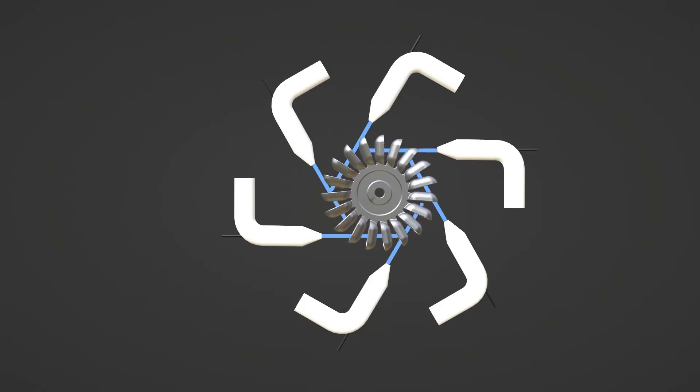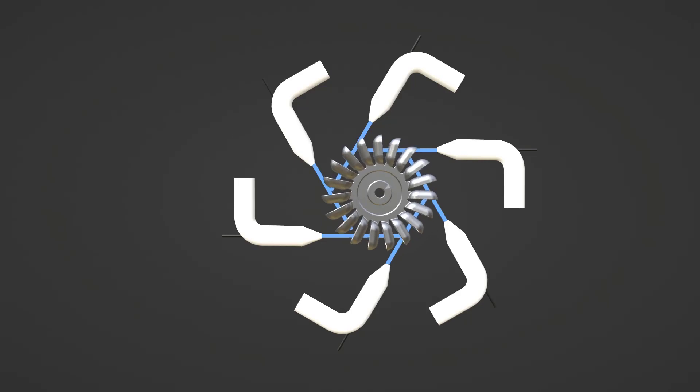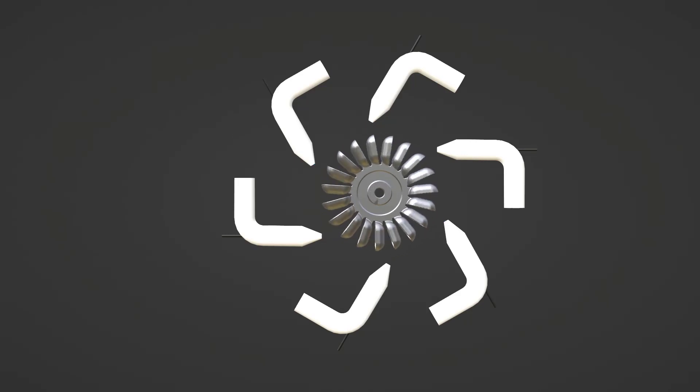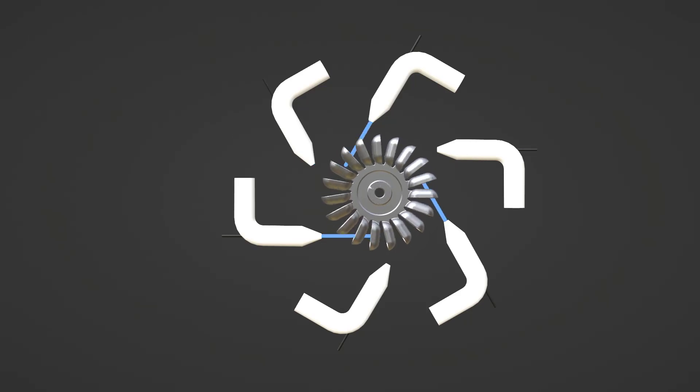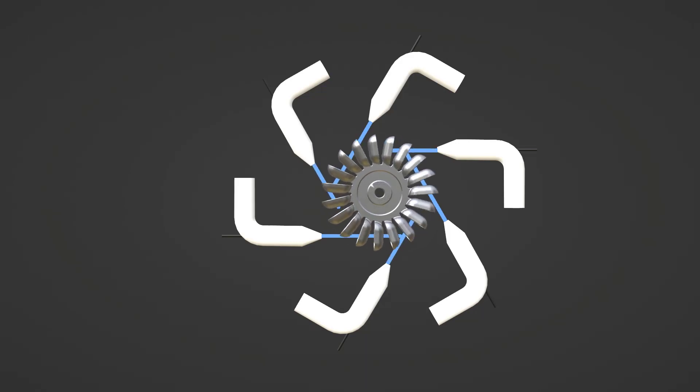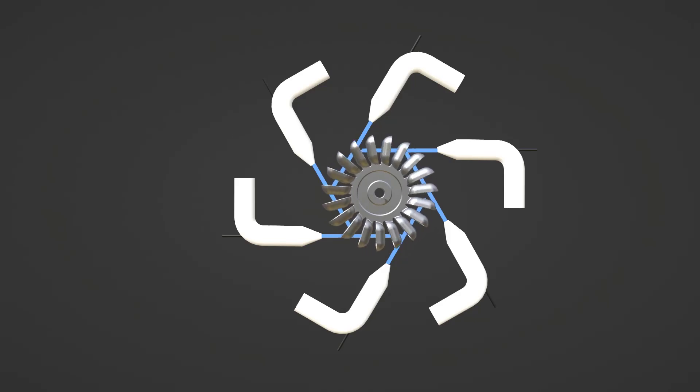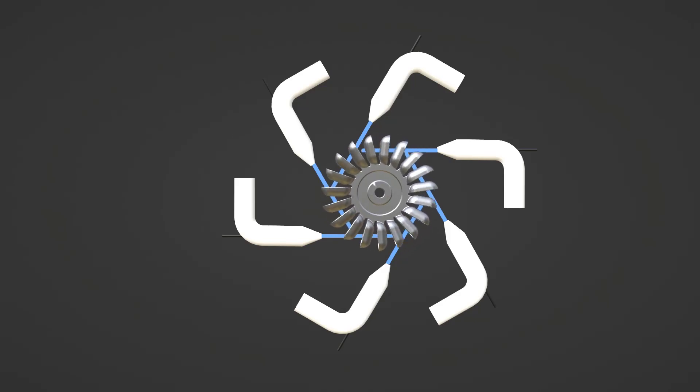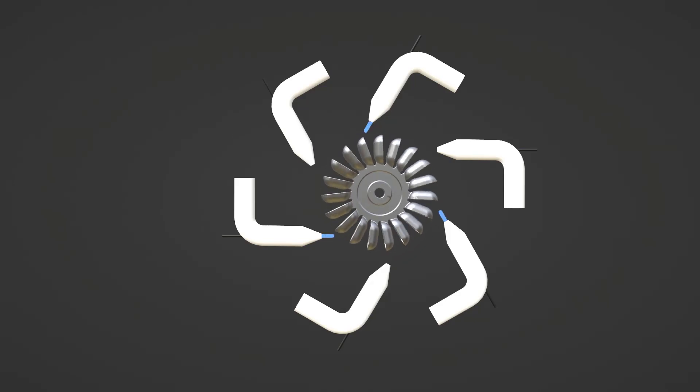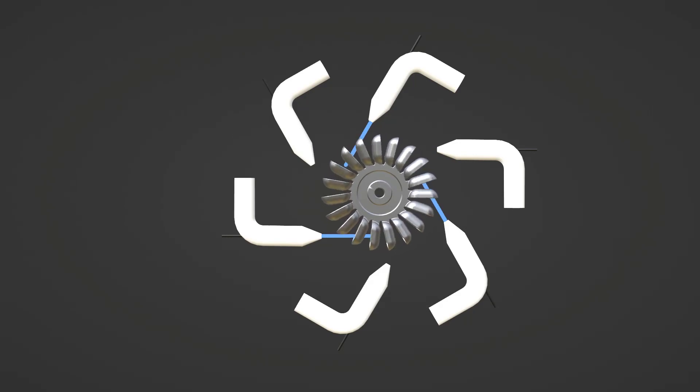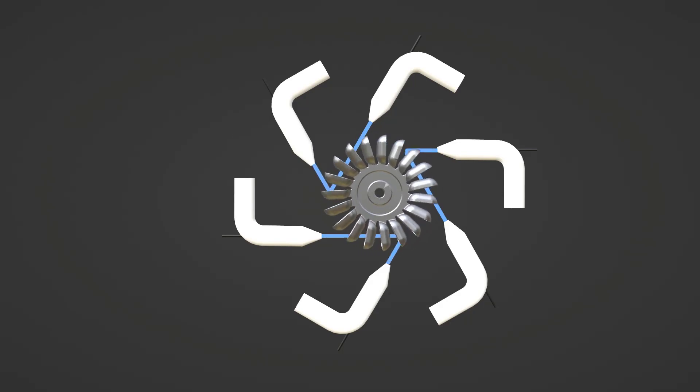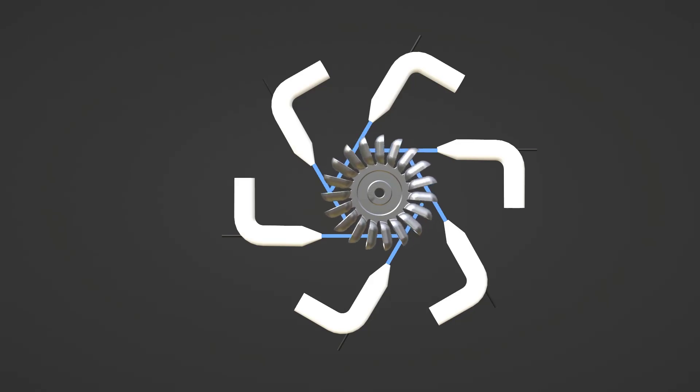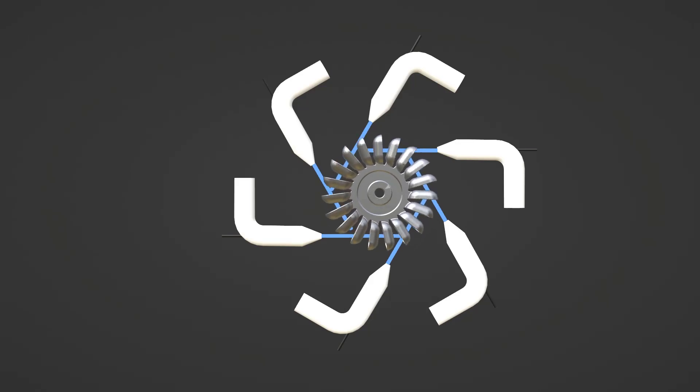After that, you suddenly start all the remaining nozzles. In my case, three at the same time. The question is why? The reason is so that you don't reach critical velocity. Suppose you start sequence by sequence your nozzles, what will happen is there will be a time when your Pelton wheel shaft will reach critical velocity and it will destroy.